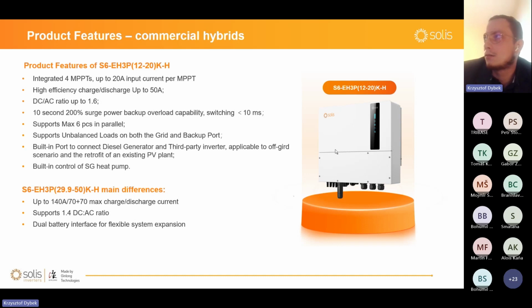Also, about the biggest dual battery interface supports a little bit less than 1.4 DC-AC ratio. Actually, right now we are heading up to 2. So if you would use a 50 kilowatt inverter, you can easily set 100K on DC side right now. And max discharge current is 70 amps per port for the battery.